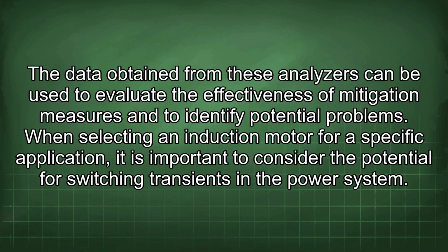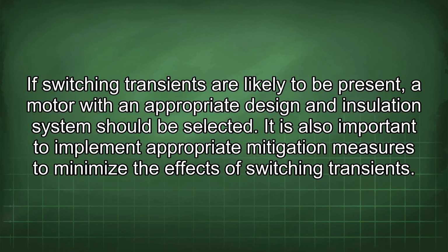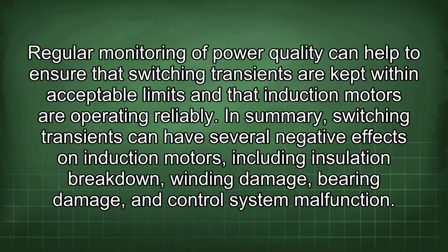When selecting an induction motor for a specific application, it is important to consider the potential for switching transients in the power system. If switching transients are likely to be present, a motor with an appropriate design and insulation system should be selected. It is also important to implement appropriate mitigation measures to minimize the effects of switching transients. Regular monitoring of power quality can help to ensure that switching transients are kept within acceptable limits and that induction motors are operating reliably.